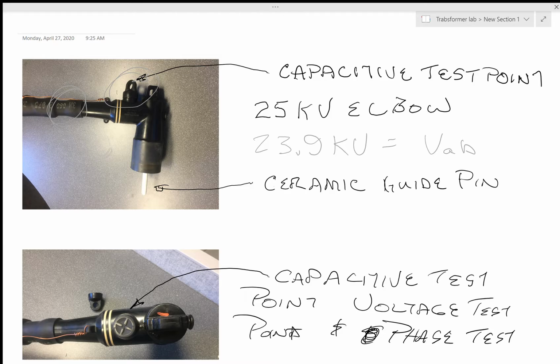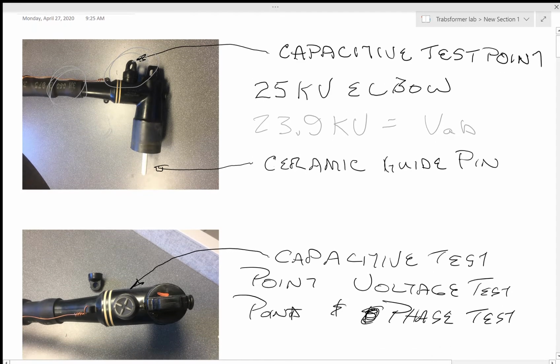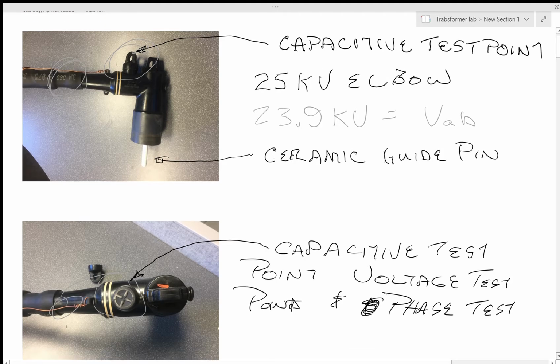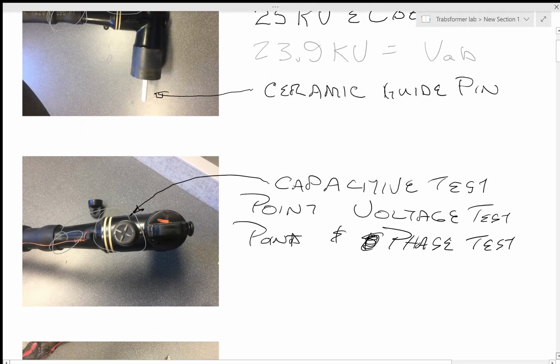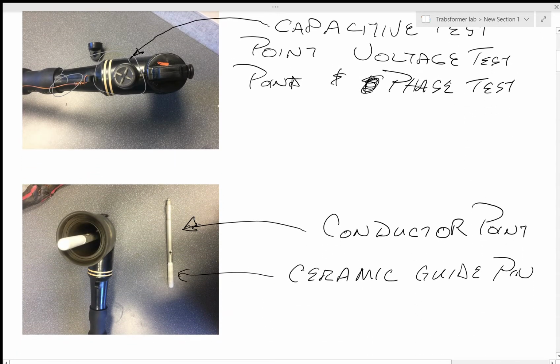Anyway, here's with the cap off, here's the capacitive test point. Like I say, you can check and see exactly what the voltage is, or check phasing on it. This is a ground wire. It just grounds the elbow. Not a big thing, but you do need your ground wires. Here is the ceramic guide pin. This is the ceramic part of the guide pin, and this is the actual conductor of the guide pin.